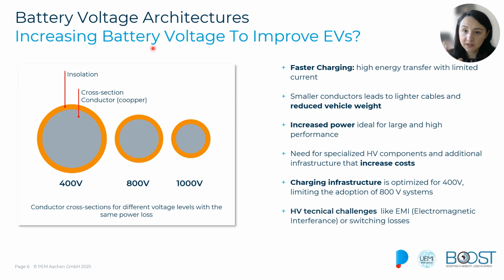To understand the benefits of increasing the voltage in the electric system, let's first take a look at the relationship between the voltage level and the size of the conductors. This comparison is illustrated here, where we examine the conductor cross-section for different voltage levels with the same power loss. The electrical power loss in a conductor is primarily due to the resistance and the current going through that conductor.